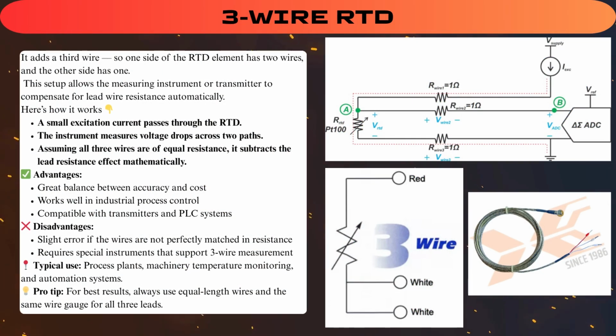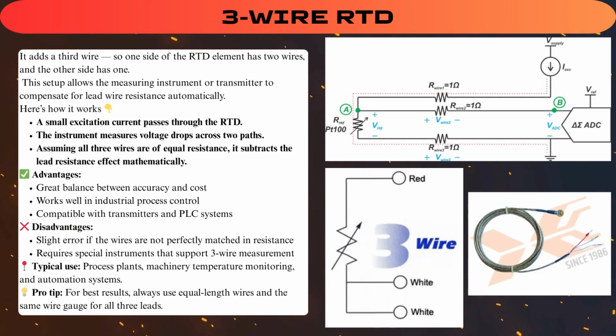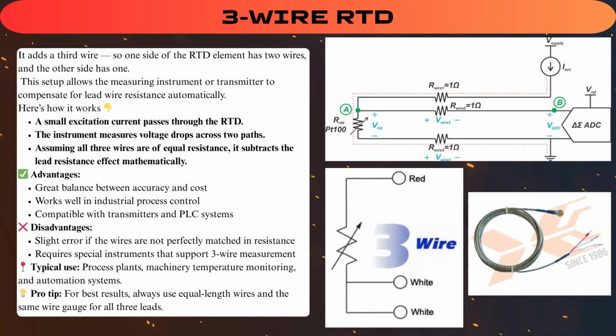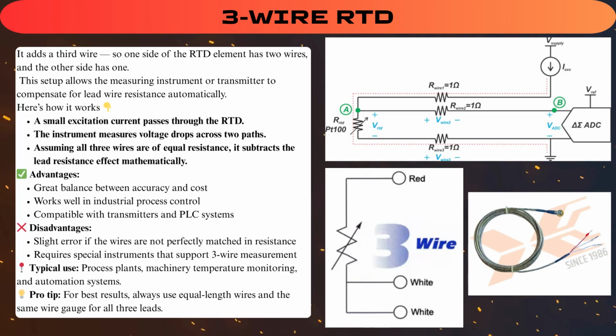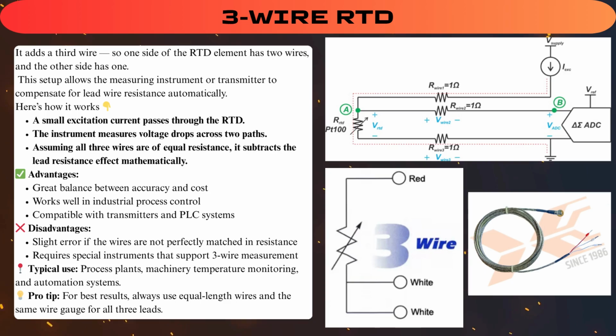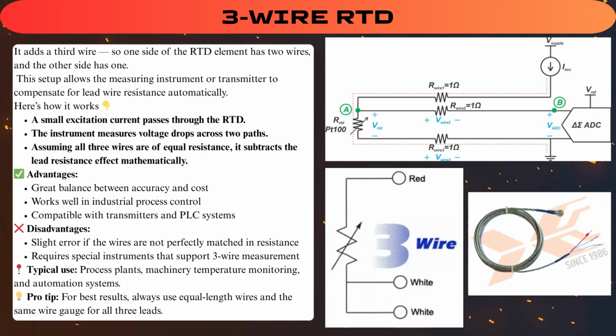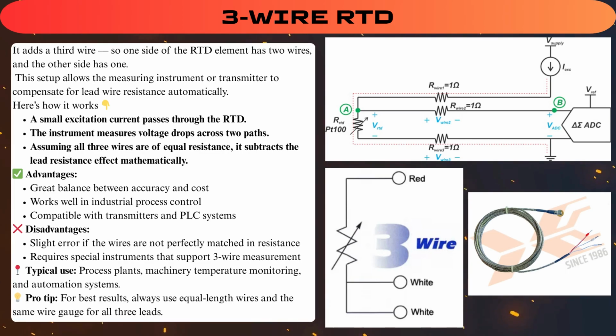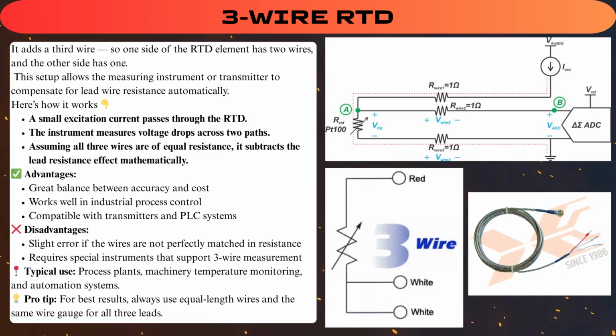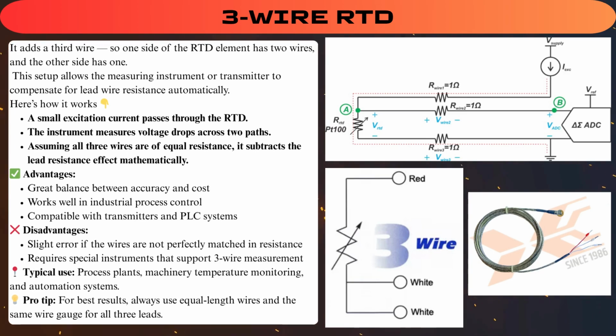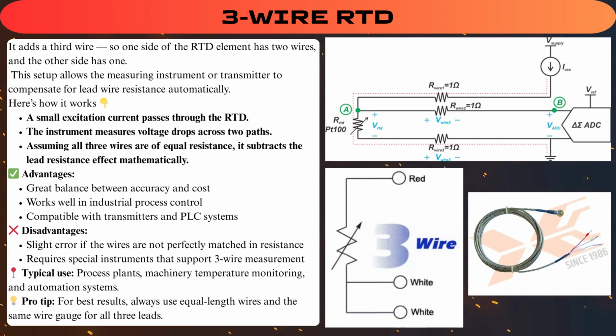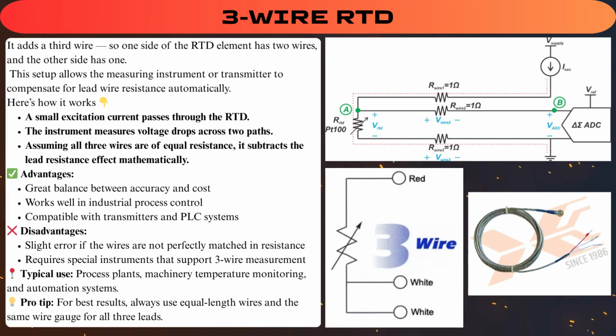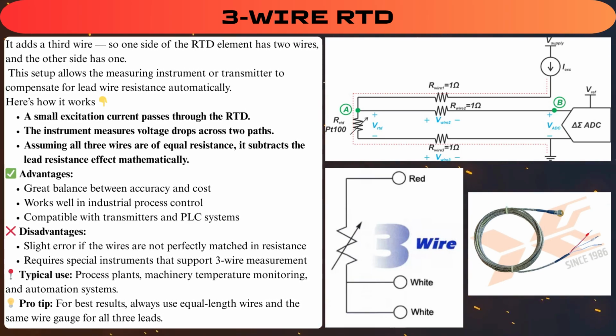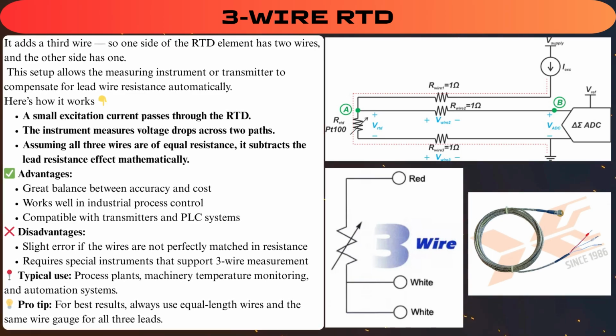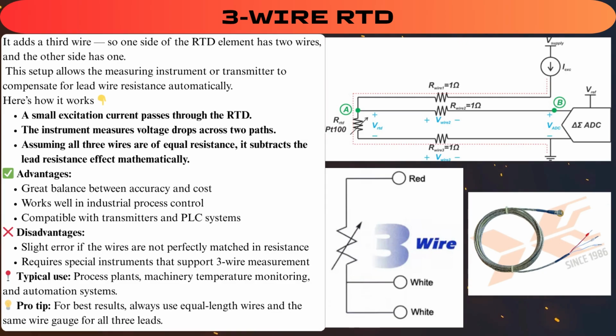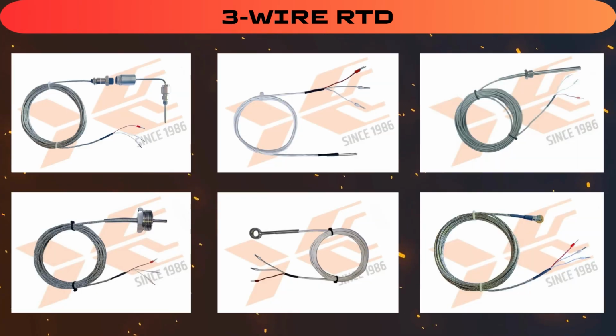3-wire RTD. Now comes the most widely used, the 3-wire RTD configuration. It adds a third wire, so one side of the RTD element has 2 wires and the other side has 1. This setup allows the measuring instrument or transmitter to compensate for lead wire resistance automatically. Here's how it works. A small excitation current passes through the RTD. The instrument measures voltage drops across 2 paths. Assuming all 3 wires are of equal resistance, it subtracts the lead resistance effect mathematically.